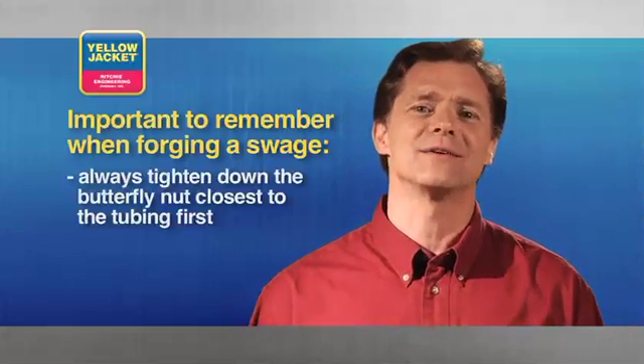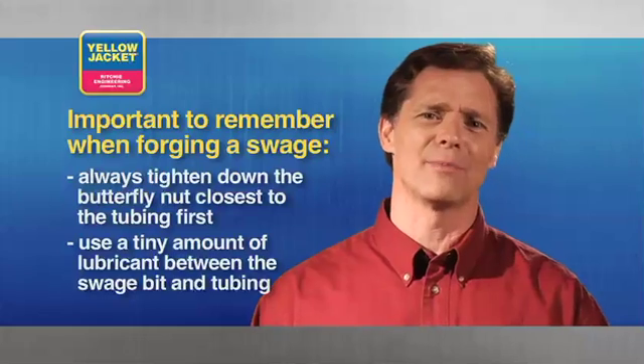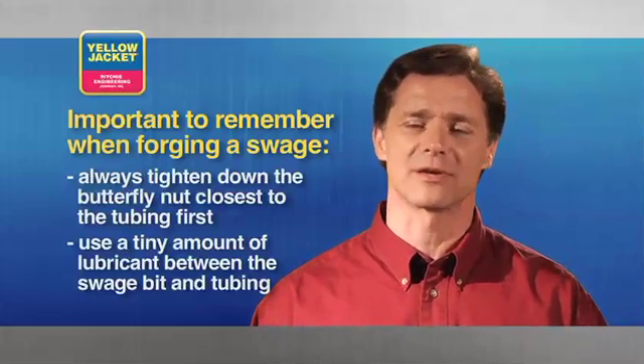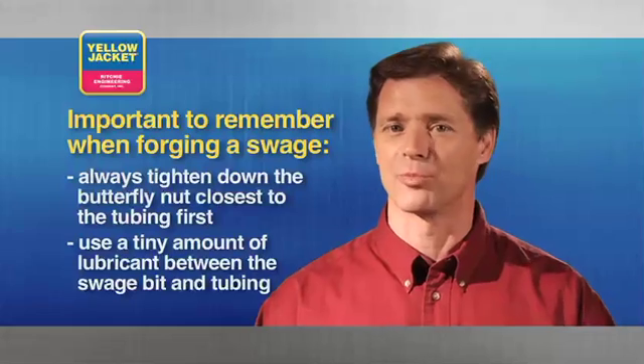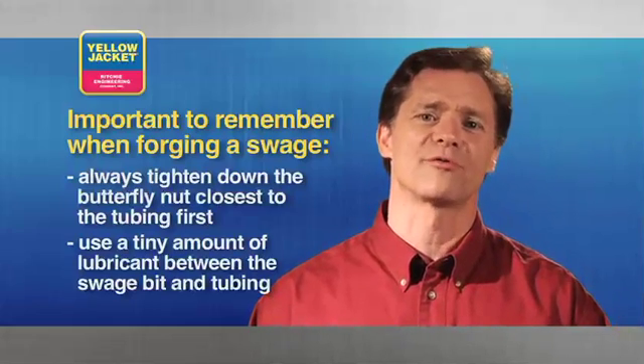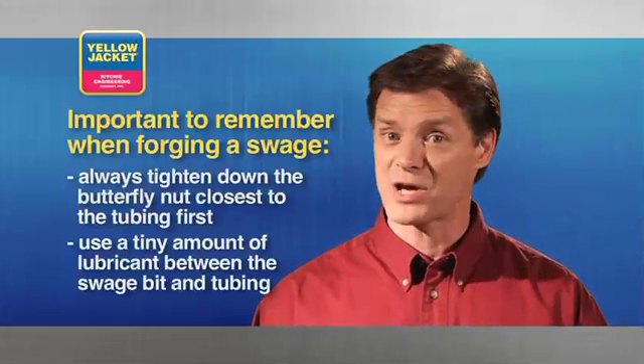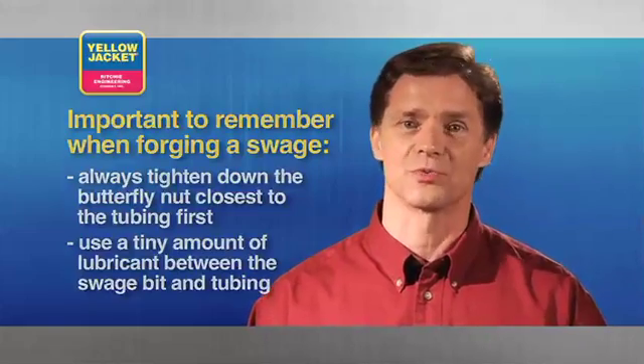It's also a good idea at this point to use just a tiny amount of lubricant between the swage bit and your tubing. Not enough to contaminate your braze joint, just enough to offer a little lubrication, especially if you've performed a lot of swages with your bit.